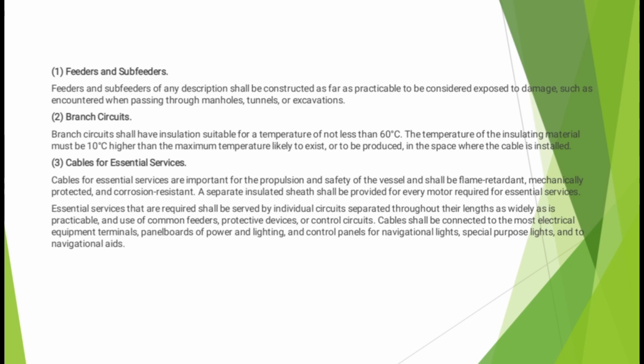Feeders and subfeeders. Feeders and subfeeders of any description shall be constructed as far as practicable to be considered exposed to damage, such as encountered when passing through manholes, tunnels, and excavation. Branch circuit. Branch circuits shall have insulation suitable for a temperature of not less than 60 degrees Celsius. The temperature rating of the insulating material must be 10 degrees Celsius higher than the maximum temperature likely to exist or to be produced in the space where the cable is installed.